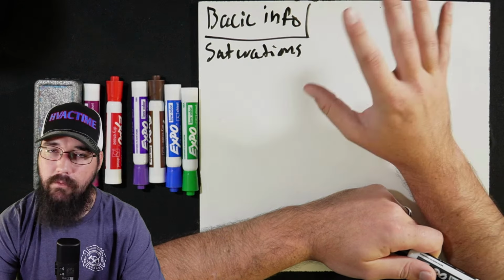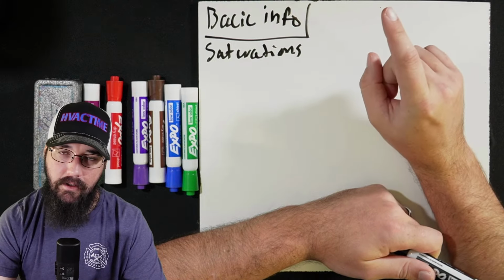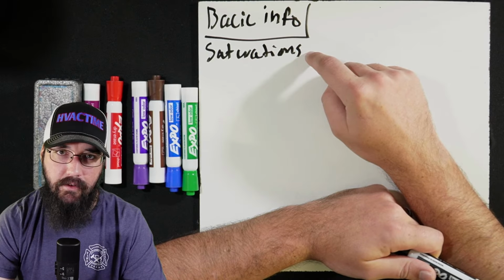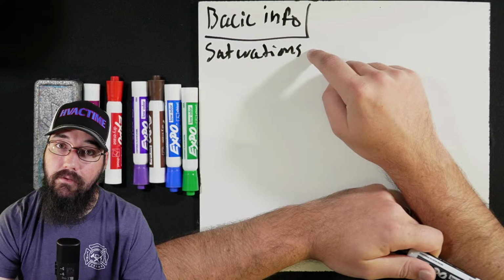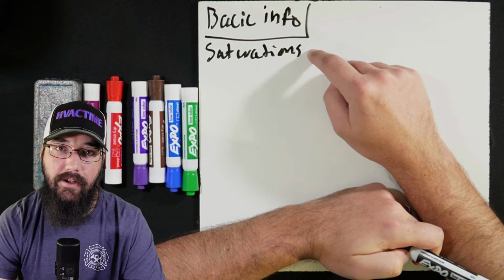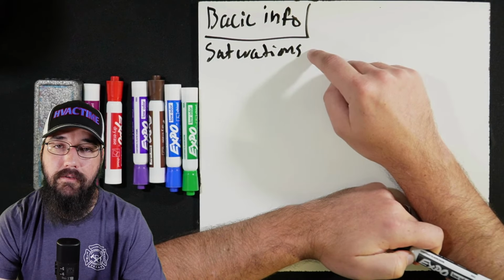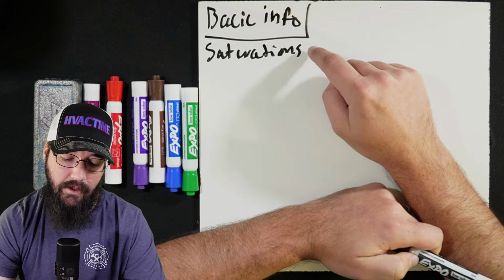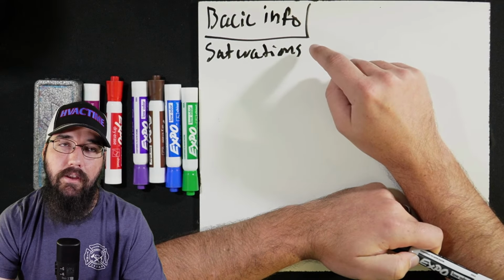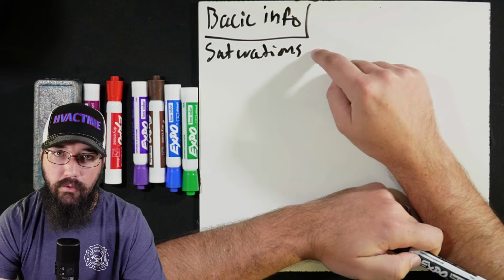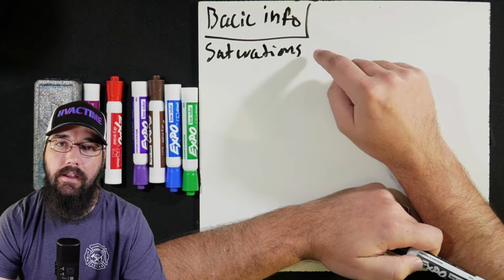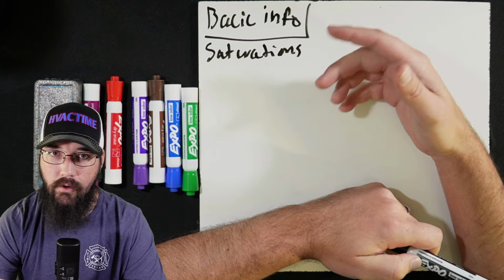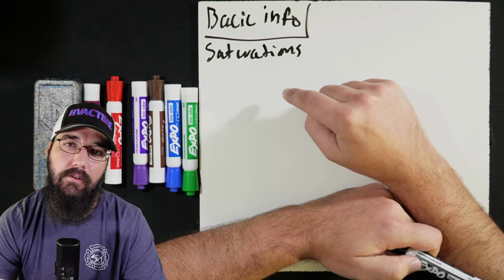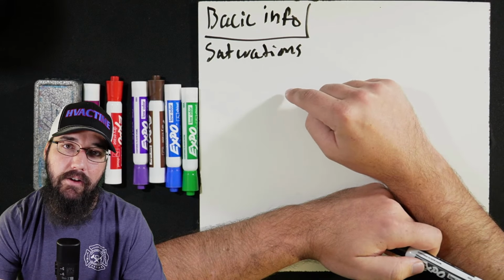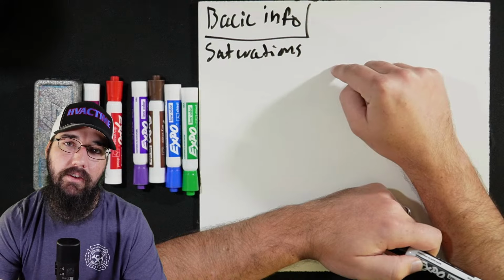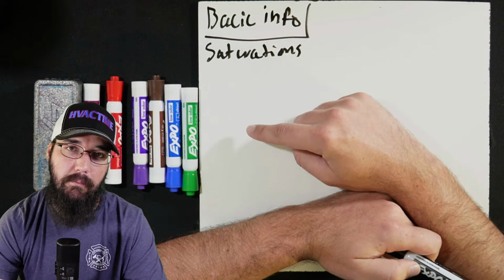Well, it's not that simple because think of it in a chiller world. First, how do we define a chiller? It has a hydronic evaporator. That's what we have as a chiller, meaning that the fluid going through the load, the liquid, is water or brine, and that water brings the heat back to the chiller, and then we process the heat into the chiller's refrigerant stream and back out.